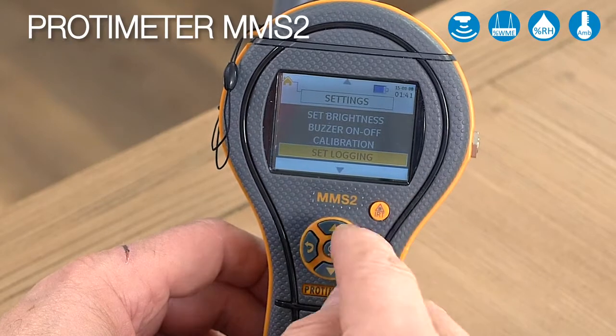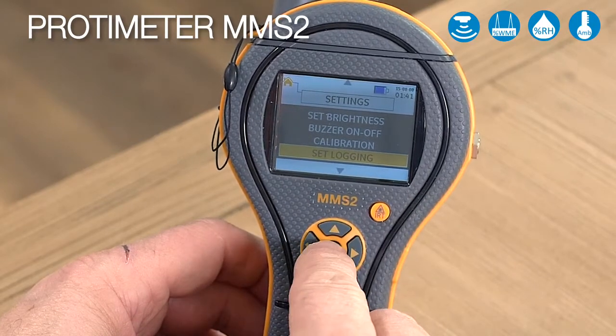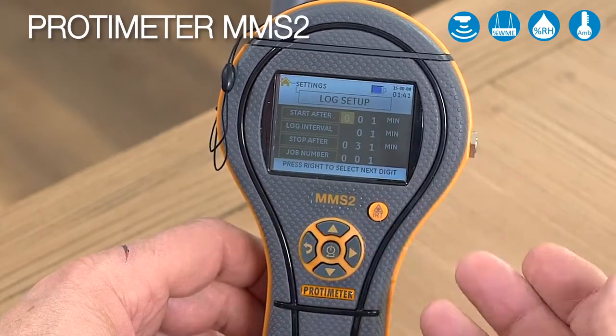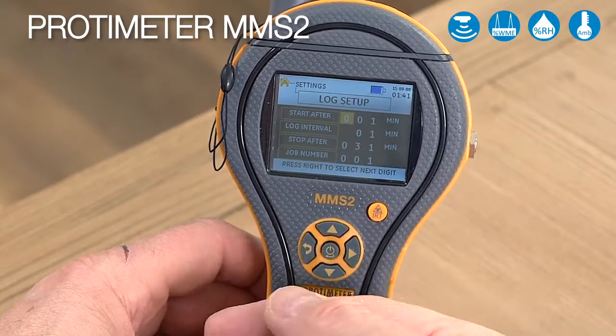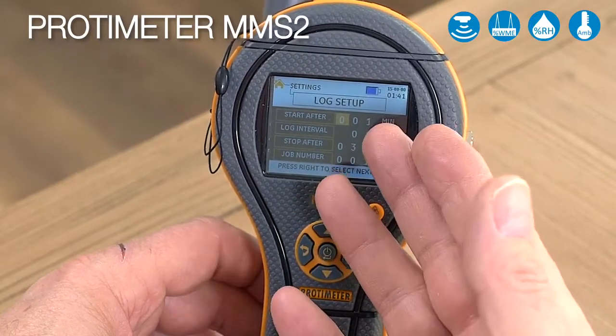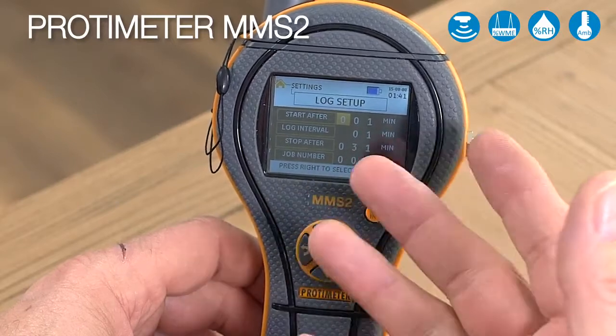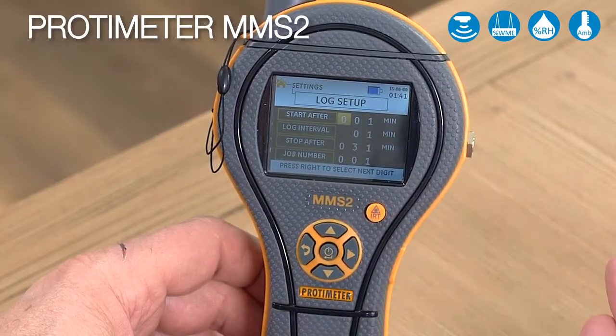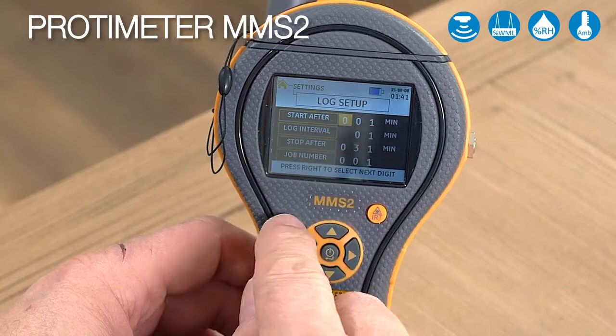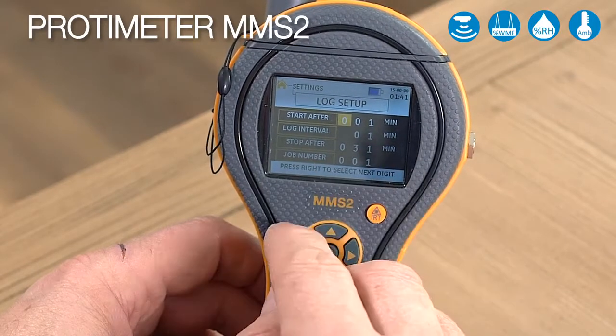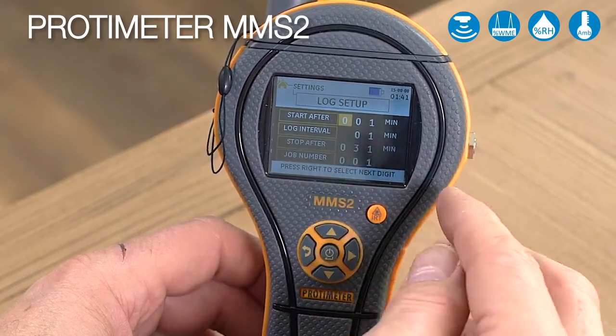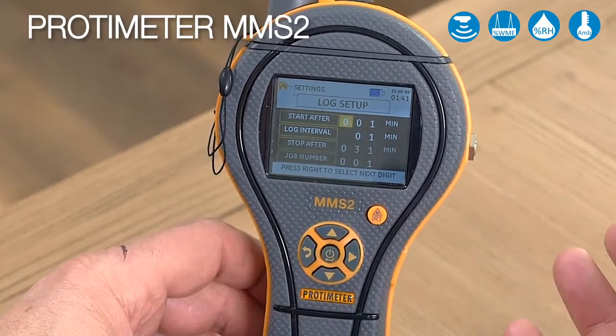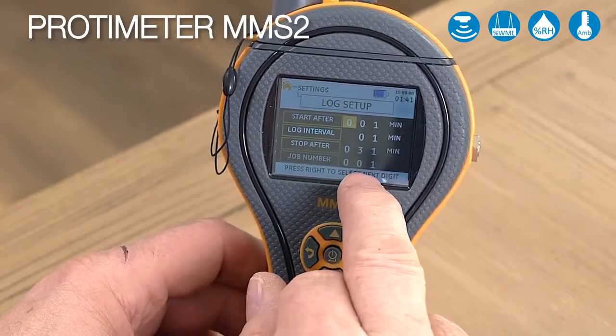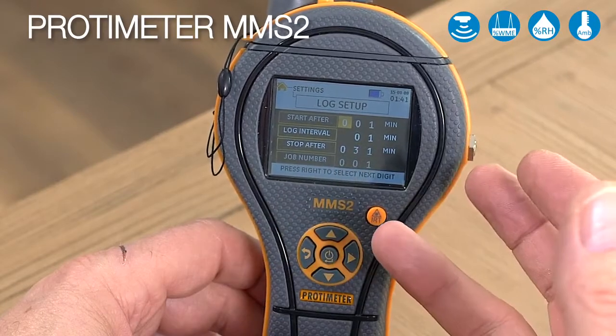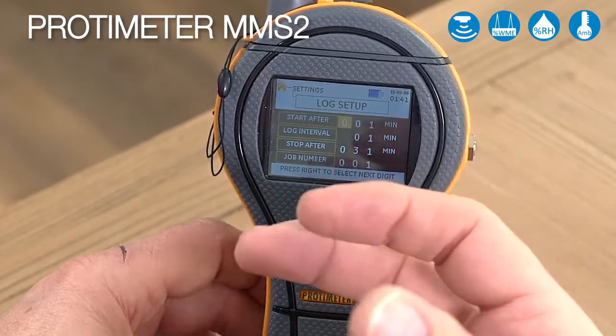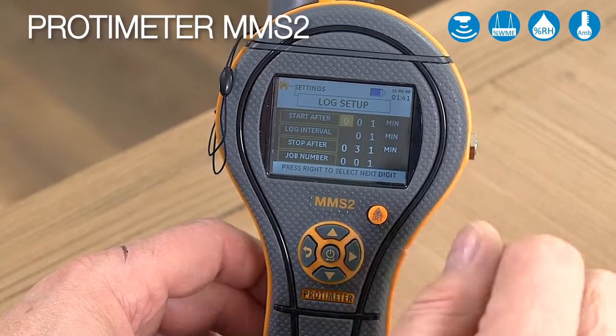We can also set our logging function within the instrument as well as on the software. If you want to log relative humidity and temperature, you can set when you want to start it - for example, start in an hour's time. You can set the logging interval, how often readings are taken, say stop after 3 hours and take no more readings, and then allocate a job number so you can save that data for a particular site under an individual number.